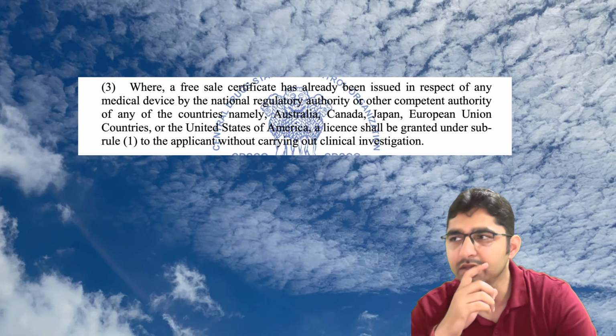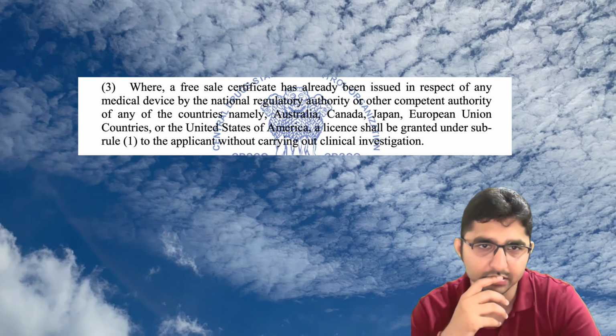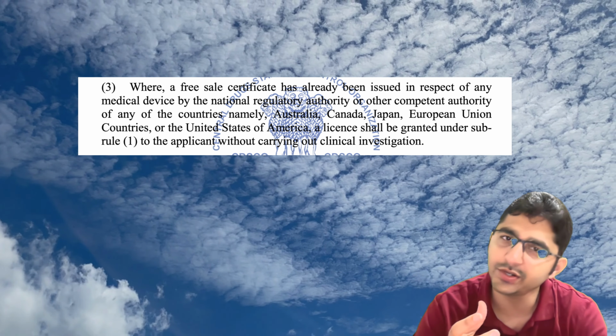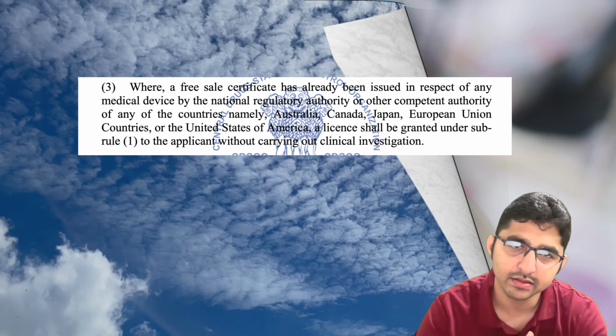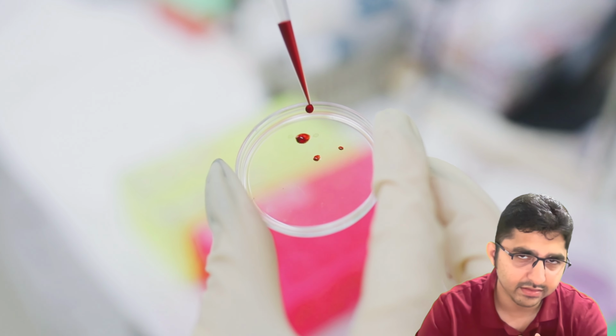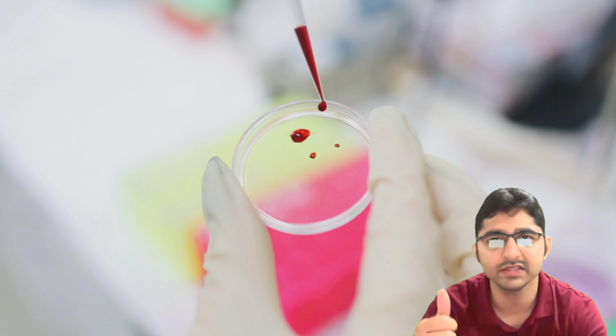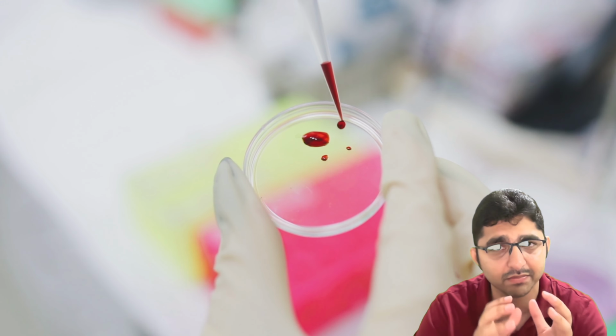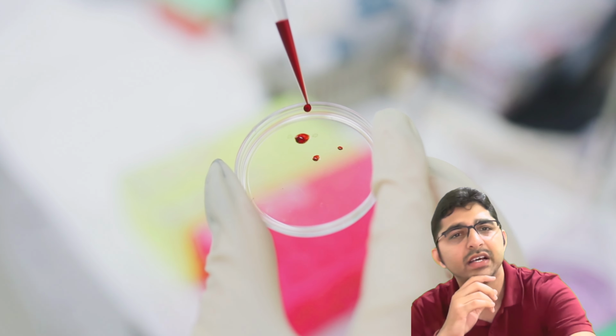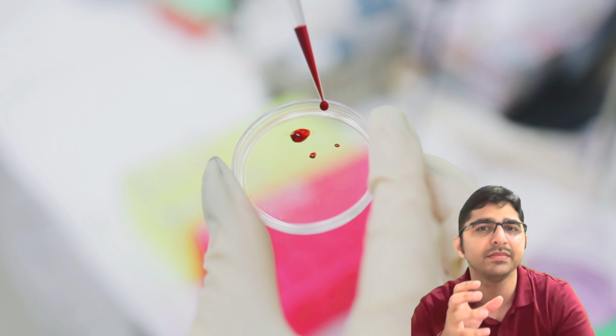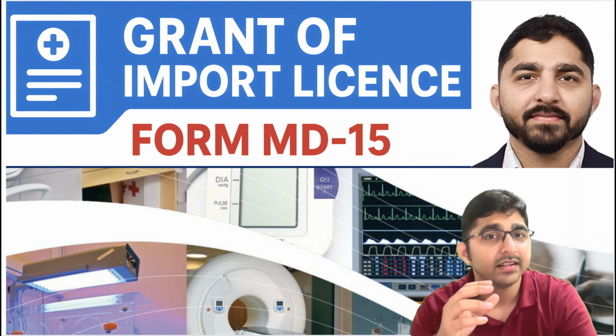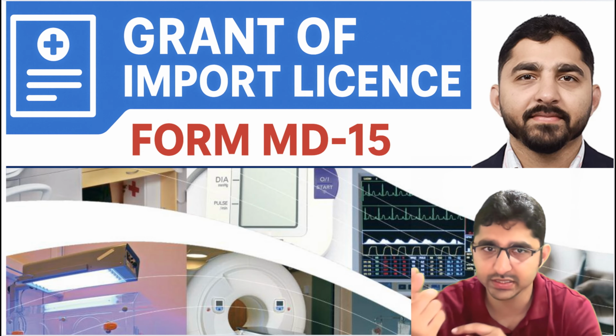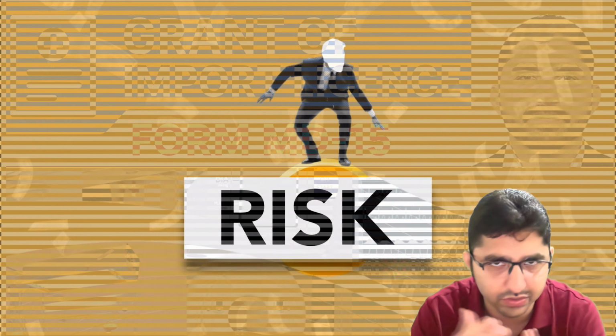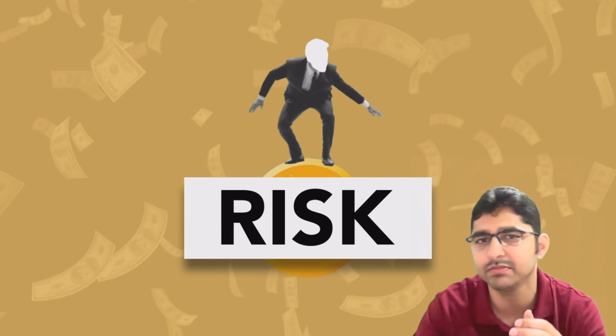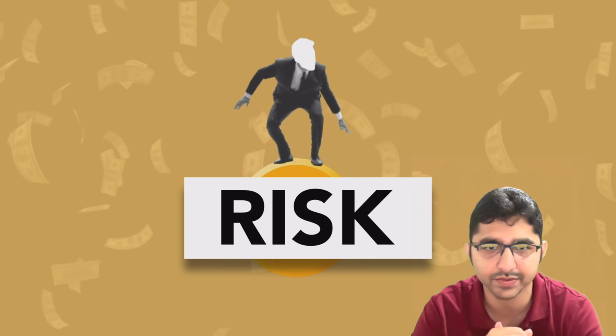But what about the medical devices coming from other countries? For devices imported from other countries, for class C and D, the license is granted only after clinical investigation in India proves that it complies with safety and effectiveness. Whereas for class A and B, the license may be granted if safety and performance is proven through published data, clinical investigation in the country of origin, or a free sale certificate from the country of origin. So it is based on the criticality or the classification of the medical device, right?